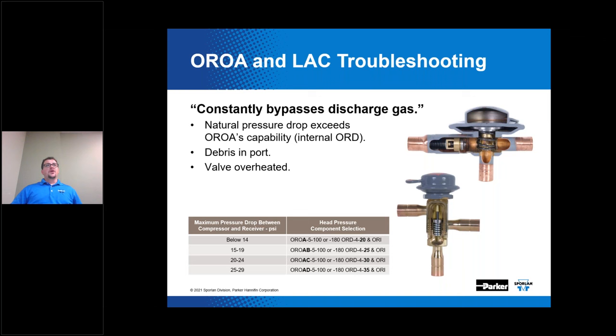More troubleshooting for the OROA and LAC: constant bypassing of discharge gas could happen due to the natural pressure drop exceeding the OROA's capability. The internal ORD opens on rise of differential pressure, so you need to ensure the pressure drop between the compressor and the receiver is below the setting of that ORD. Another reason for constant bypassing could be debris in the port or overheating of the valve. You can order an inlet strainer purchased separately that can be installed in the LAC4 and the OROA if desired.